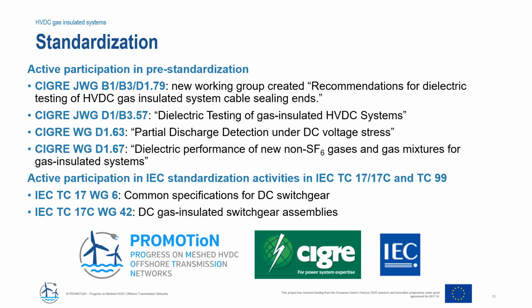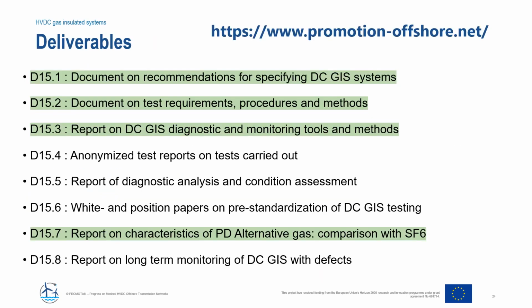Also, in the IEC standardization activities, the Work Package 15 members are involved, especially in IEC TC17, TC17C and TC99. For instance, in Working Group 6, Common Specification for DC Switchgear, as well as in Working Group 42, DC gas-insulated switchgear assemblies. I want to mention also that Work Package 15 has prepared in total 8 reports. 4 reports are already published. The document on recommendations for specifying DC GIS systems, a document on test requirements, procedures and methods, a report on DC GIS diagnostic and monitoring tools and methods, as well as a report on characteristics of a PD alternative gas, comparison with SF6. 4 more reports are currently under review, and you will find all the reports latest in September on the ProMotion website.